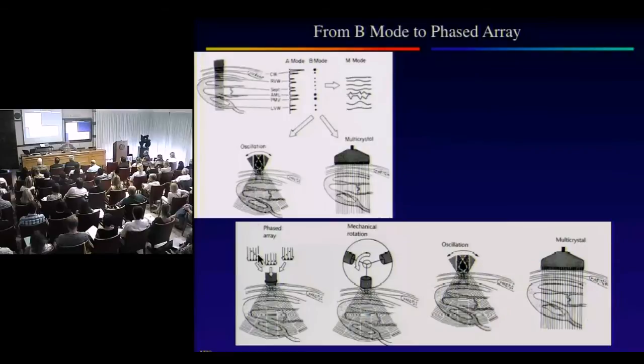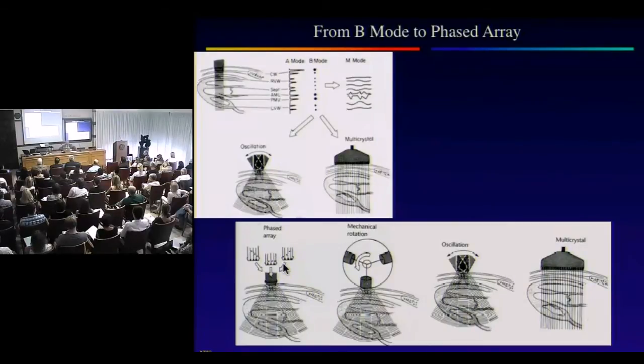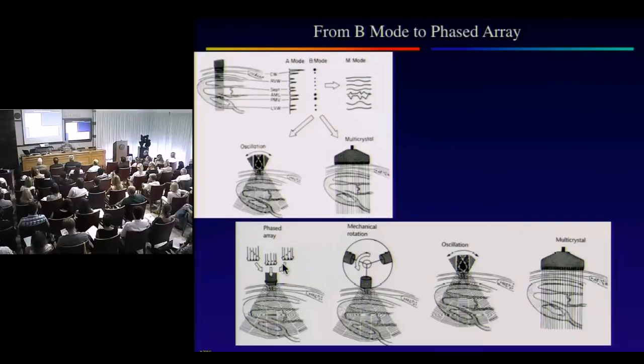Eventually, an electrical signal like radar was used to phase the signal, so that exciting the crystals in different arrays steers the beam electronically in different directions. Because we use color, CW, PW, M mode, 2D, and even 3D all simultaneously, the complexity increases with each modality. For M mode crystals it's simple, 2D is more complicated, and 3D is exponentially more complicated than 2D because the number of crystals goes up into the thousands, and each one must be modified.